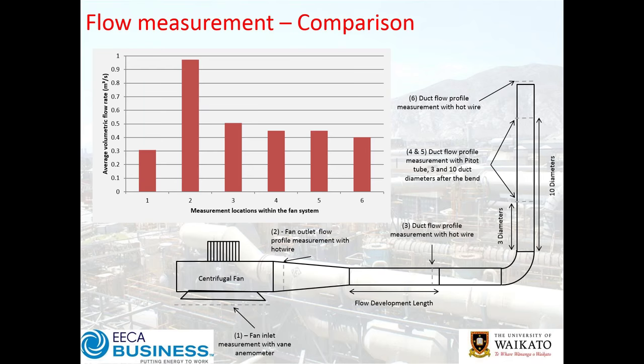Measurement 2 at the fan outlet with the hot wire quite substantially overestimates the true flow rate. The reason is that the hot wire picks up all velocity components — not just the axial component but also in-plane velocity components associated with the fan's momentum. With good duct design, this gets recovered as static pressure further down the duct. Generally when taking measurements immediately after the fan with a hot wire, you will overcompensate and record a higher velocity. In practice 20–30% overshoot is quite common; in this severe example it's nearly double.